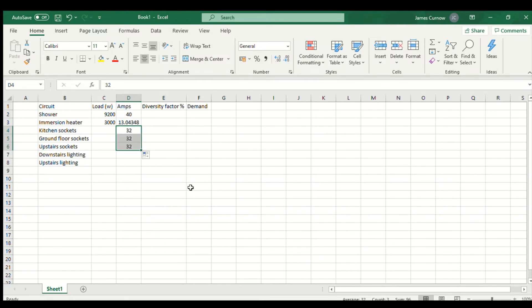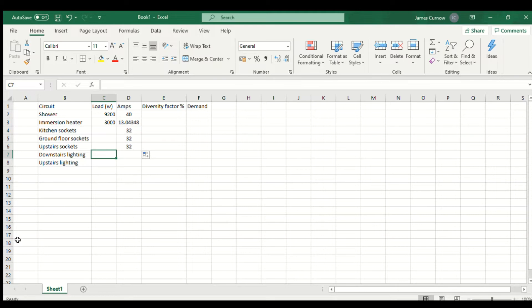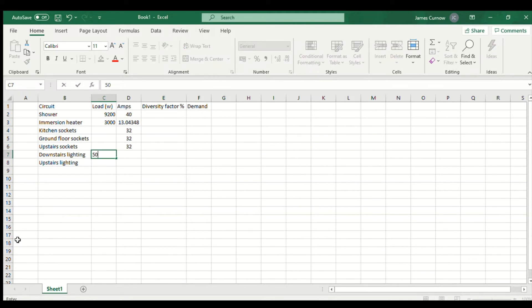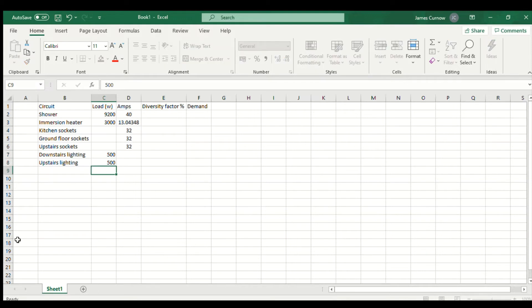For the lighting we can calculate the wattage simply by adding up the wattage of the lamps. If we don't know the wattage then I would use 100 watts for each one. But for the purpose of this example I'm just going to say 500 watts for each.